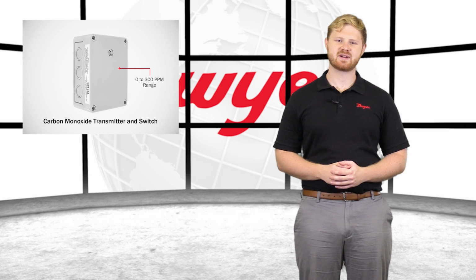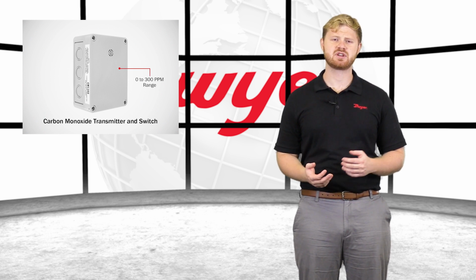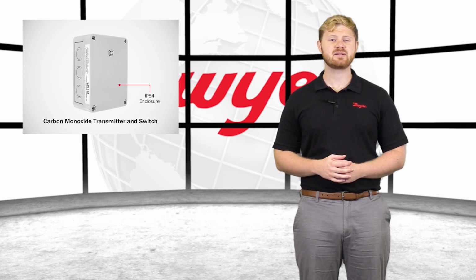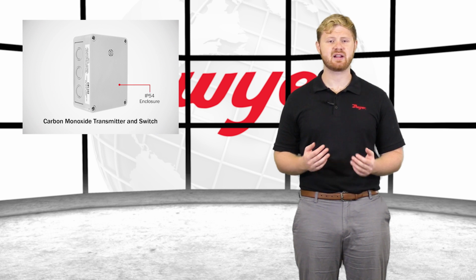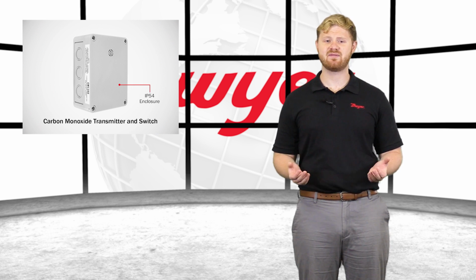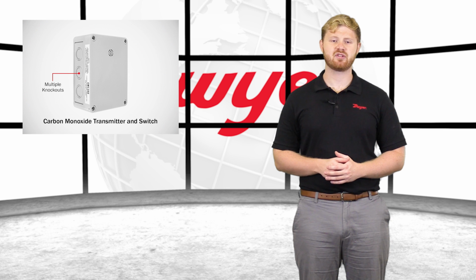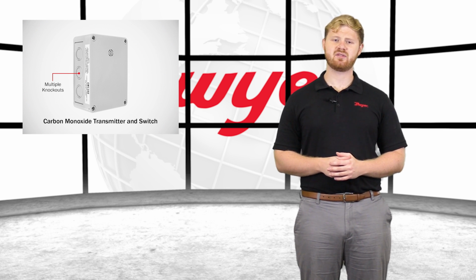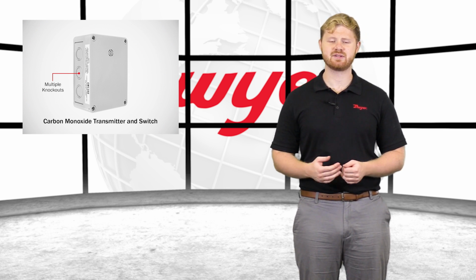This carbon monoxide transmitter offers a measurement range of 0 to 300 ppm. It is housed in a UV-resistant, glass-filled polycarbonate enclosure rated up to IP54, which also features multiple knockouts to give flexibility to the installer to determine the best location for conduit entry.